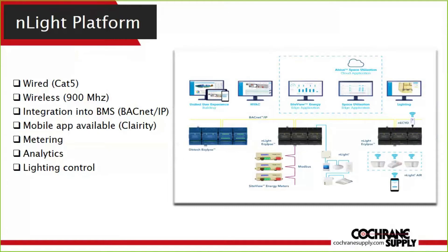The Eclipse controller is a Distech Eclypse unit specialized to work with lighting control systems, specifically nLight. Additional features available through it include metering using Rogowski coils for revenue-grade real-time power metering, reported out through a simplified dashboard. We also have analytics for space utilization — when spaces were occupied or unoccupied — and remote lighting control access via the internet. The Eclipse controller can be placed within the customer's local area network or on their cloud for remote access.